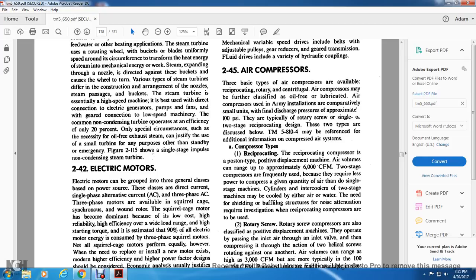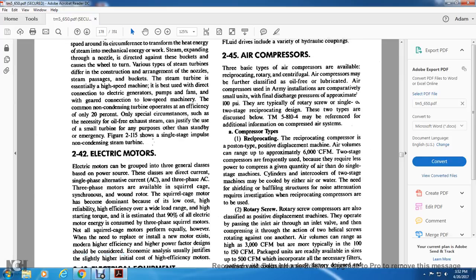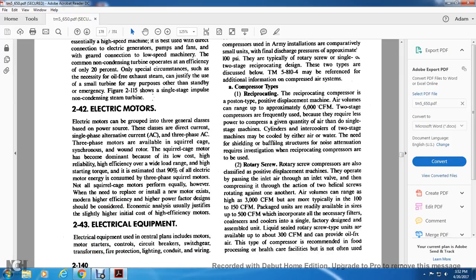Compressor types. The reciprocating compressor is the piston type with positive displacement. Machine air volumes can range up to approximately 6,000 CFM. Two-stage compressors are frequently used because they require less power to compress a given quantity of air than single-stage machines. Cylinders and intercoolers of two-stage machines may be cooled by either air or water. Noise attenuation, shielding, and baffling require investigation when reciprocating compressors are used.